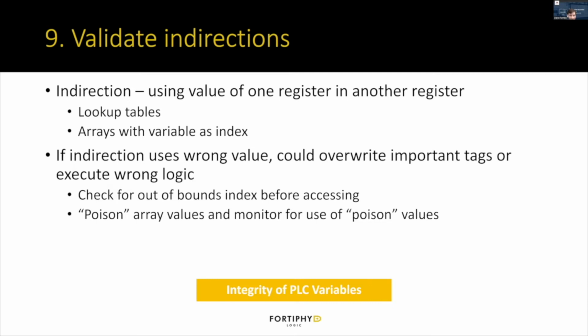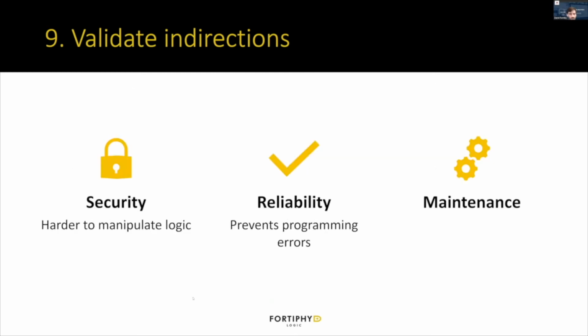The easiest way to do this is just add checks for out of bounds index before you access the array. Another, more complicated approach, which you can find in the top 20 secure PLC document, is poisoning array values and using that to monitor for accidental overrides of the poison values. But you can also just check for out of bounds indexing. For security, this makes it harder to manipulate the logic, since the attacker has to really understand your program to cause problems. For reliability, it helps prevent programming errors. If you didn't write the logic quite right, it helps prevent and detect when those indirections might be going wrong.